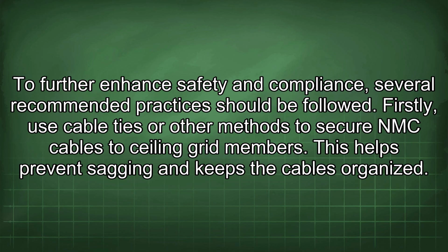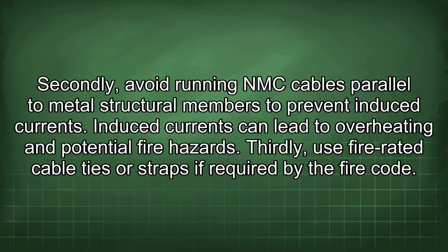To further enhance safety and compliance, several recommended practices should be followed. Firstly, use cable ties or other methods to secure NMC cables to ceiling grid members. This helps prevent sagging and keeps the cables organized. Secondly, avoid running NMC cables parallel to metal structural members to prevent induced currents. Induced currents can lead to overheating and potential fire hazards.